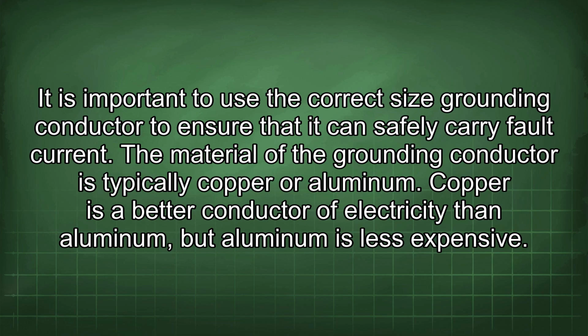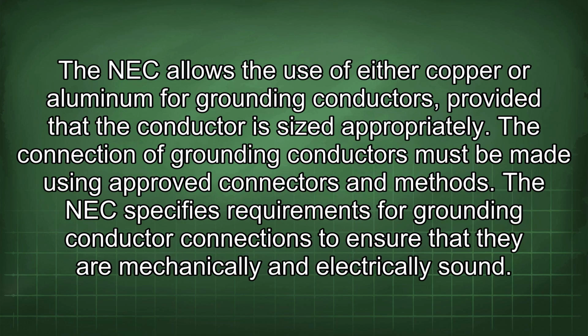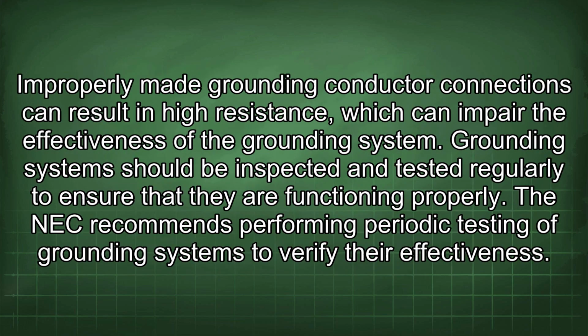Copper is a better conductor of electricity than aluminum, but aluminum is less expensive. The NEC allows the use of either copper or aluminum for grounding conductors, provided that the conductor is sized appropriately. The connection of grounding conductors must be made using approved connectors and methods. The NEC specifies requirements for grounding conductor connections to ensure that they are mechanically and electrically sound. Improperly made grounding conductor connections can result in high resistance, which can impair the effectiveness of the grounding system.